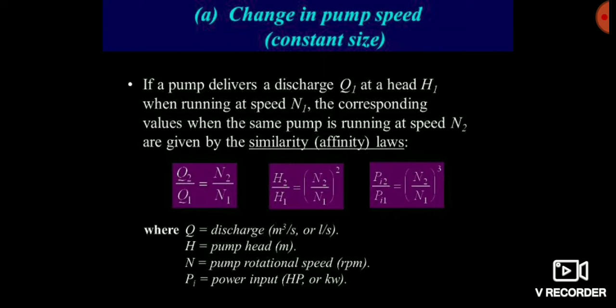The third relationship: power is directly proportional to the running speed to the power 3. If the running speed is double, then the power is going to be eight times.